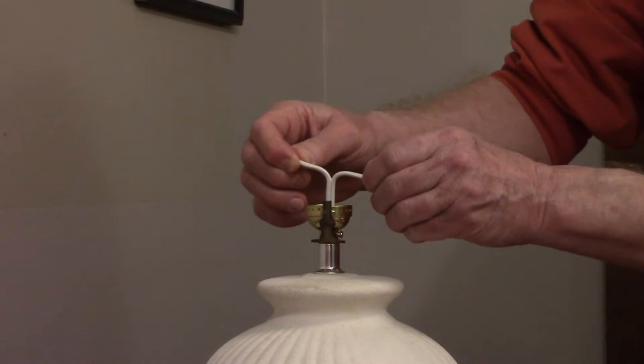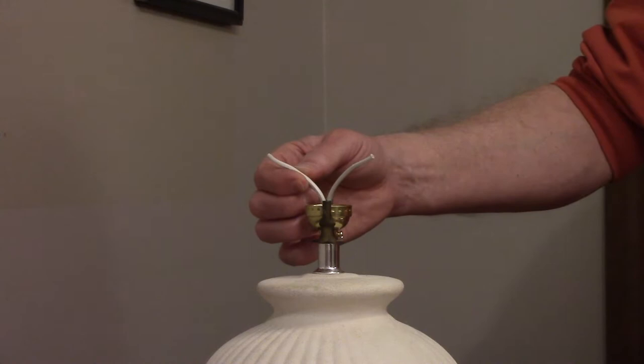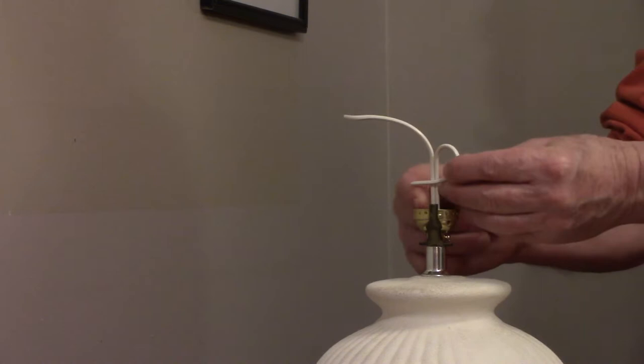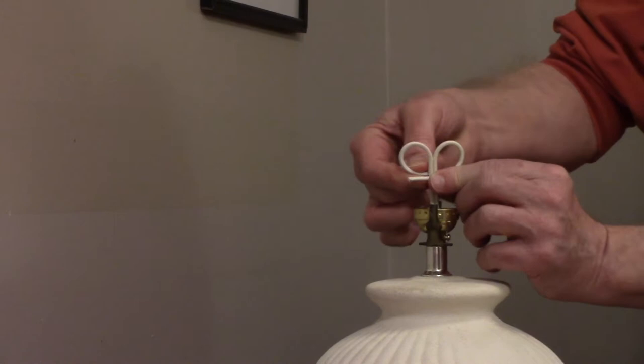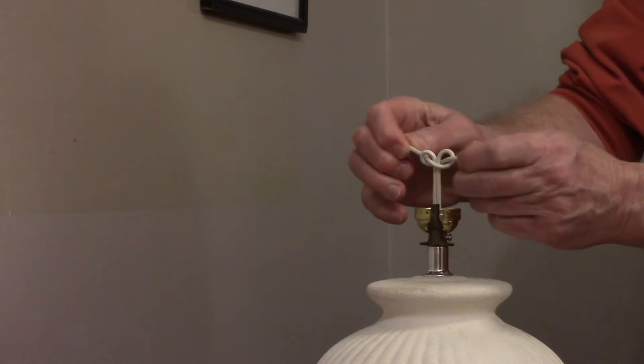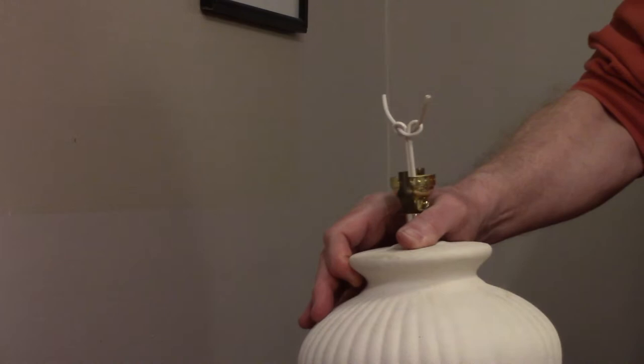We need to create an underwriter's knot. To create an underwriter's knot, you're going to take one wire and loop it down in front of the cord. Take the other wire and loop it down in back of the cord, and then you're going to pull the ends through the loops you've created. Pull it into a loose knot. You can pull down on the cord to get the knot in the bottom of the base.